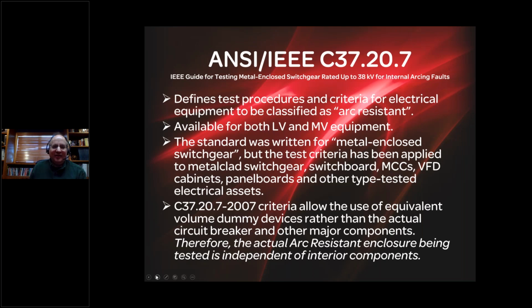So when we look at C37.20.7, what is it? The standard is ultimately there to define test procedures and test criteria, the outcome of tests, which define what can then be classified as what we call arc resistant. Now, it was originally written for metal enclosed switchgear, but it has subsequently been applied across industry on all types of equipment: switchboards, low voltage and medium voltage equipment together with switchgear, motor control centers, variable frequency drive cabinets, panelboards, and many other types of type tested equipment.